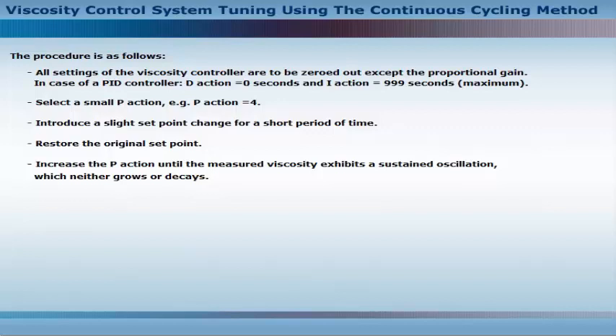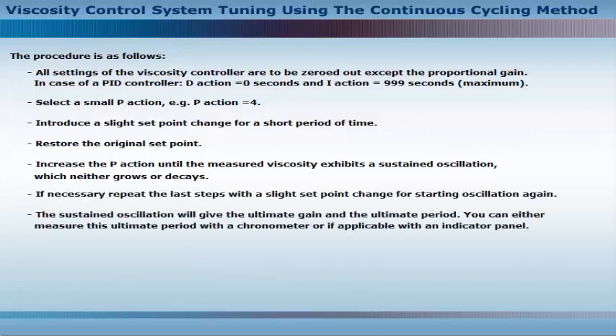Introduce a slight set-point change for a short period of time. Restore the original set-point. Increase the P-action until the measured viscosity exhibits a sustained oscillation which neither grows or decays. If necessary, repeat the last steps with a slight set-point change for starting the oscillation again.